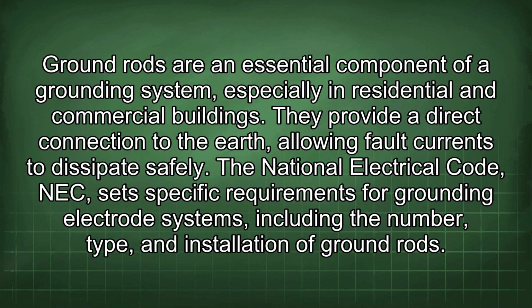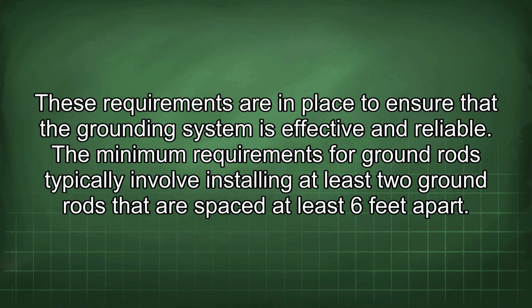Ground rods are an essential component of a grounding system, especially in residential and commercial buildings. They provide a direct connection to the earth, allowing fault currents to dissipate safely. The National Electrical Code, NEC, sets specific requirements for grounding electrode systems, including the number, type, and installation of ground rods. These requirements are in place to ensure that the grounding system is effective and reliable.